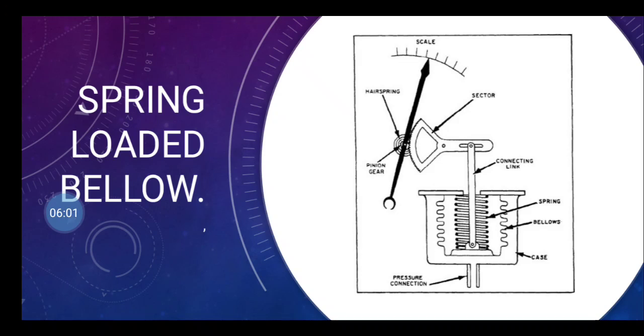The pressure acts on the bellow and thus it is compressed. The free end starts moving against spring tension. The rod transmits the motion to the pointer, which moves on the scale to indicate the reading of the pressure. The rod transmits the motion of the pointer, which moves on the scale to indicate the reading of pressure.